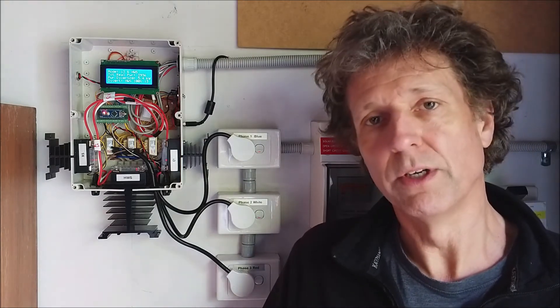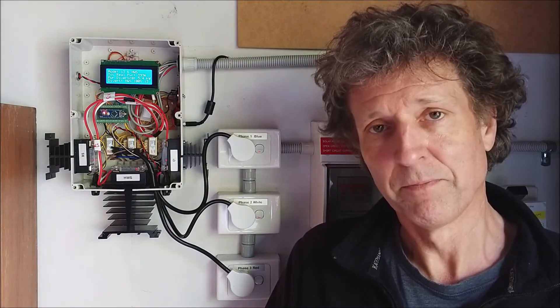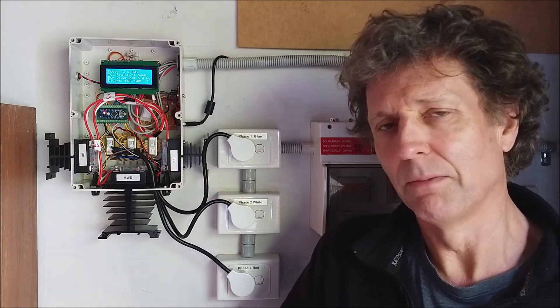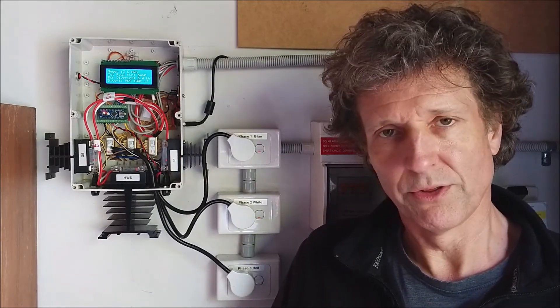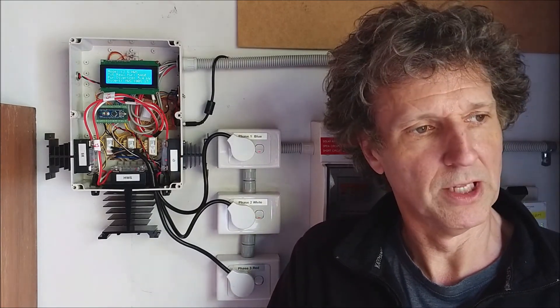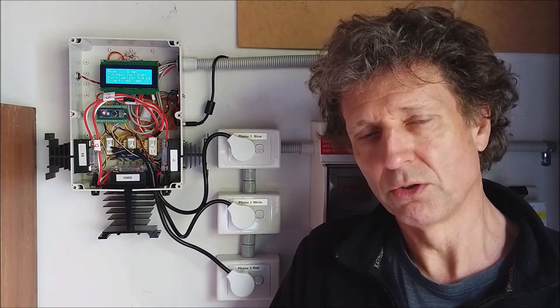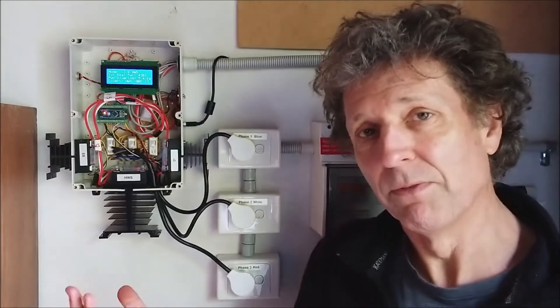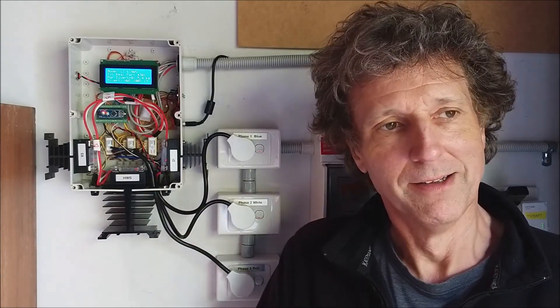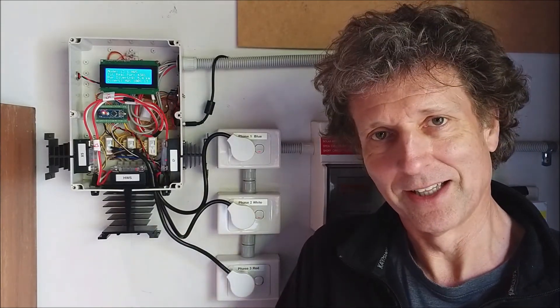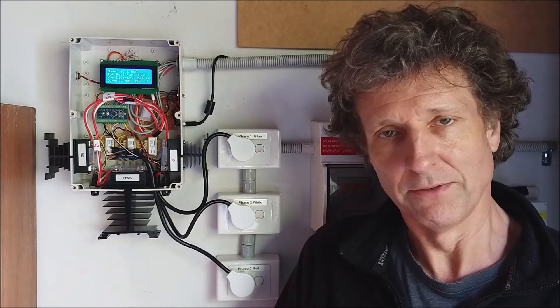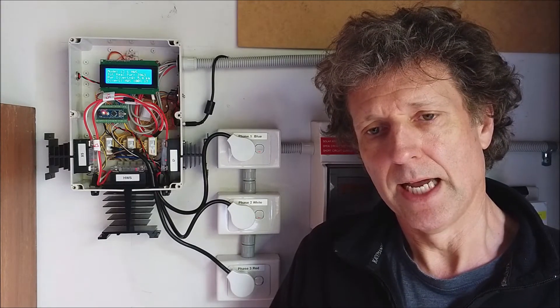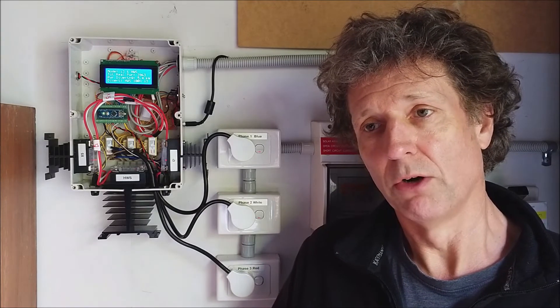So the two would essentially offset each other and this is the basis, and some people might call this pulse width switching or pulse width modulation, others would call it burst switching which it is, it's just a more rapid form of switching but it's not super rapid. We're not talking kilohertz here or anything like that, we're talking samples every five seconds.